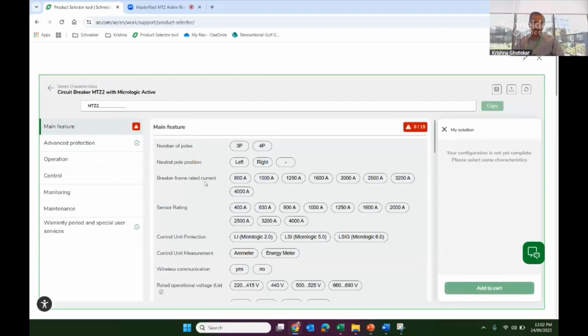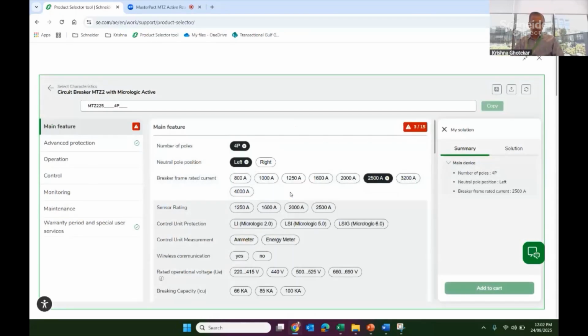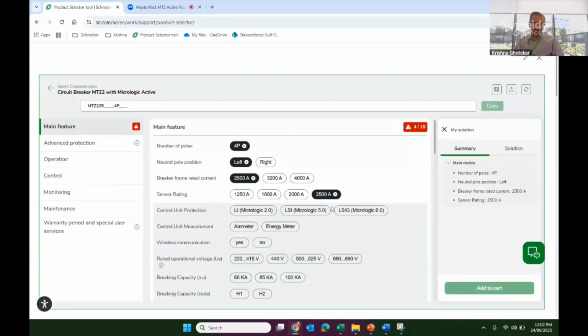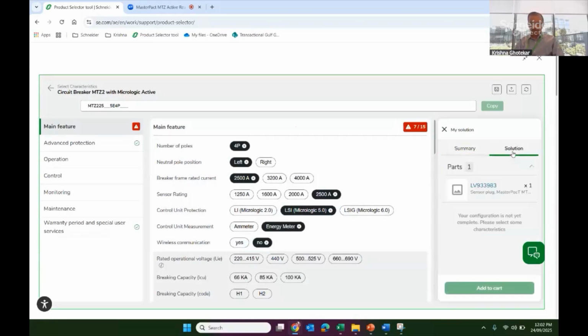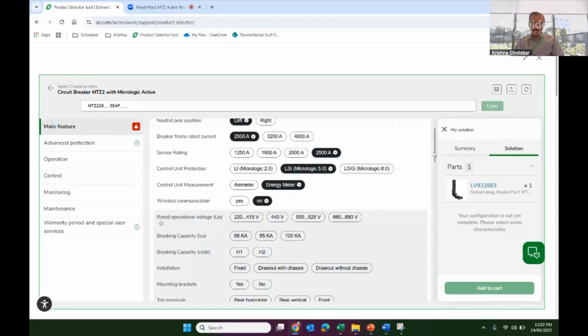Now inside that, there are some standard products. So the product code, what I was referring to, will come at the top. Let's say I want a 4-pole breaker with the neutral position, let's say left side, 2500 ampere, with a rating plug also 2500, because sometimes, let's say, initially the load is low, you can set a lower rating plug. Trip unit: you want LI, LSI or LSIG, let's say LSI. Energy metering. Now here you can select if you want wireless communication. Yes, so the W will be added for wireless, or I will say no, I want without communication. On the right side in the solution, the part number will keep on adding for the breaker.